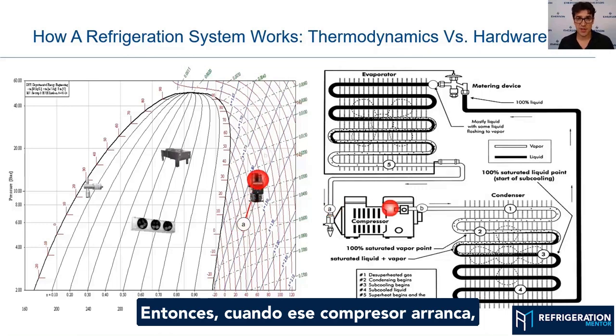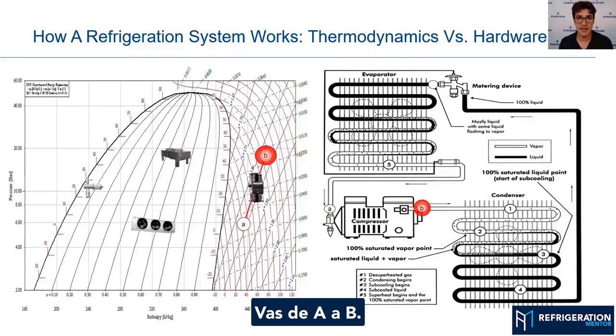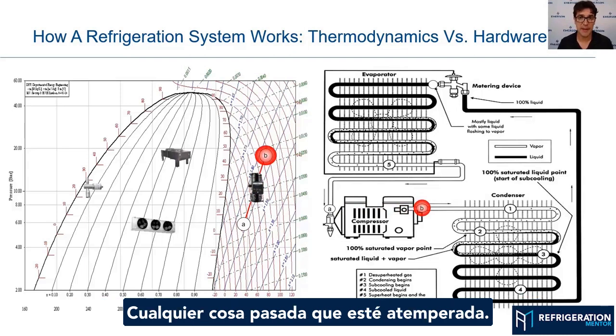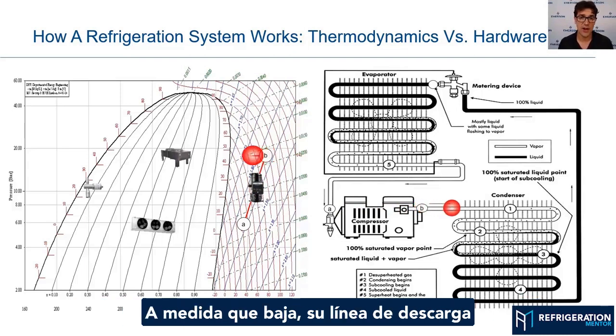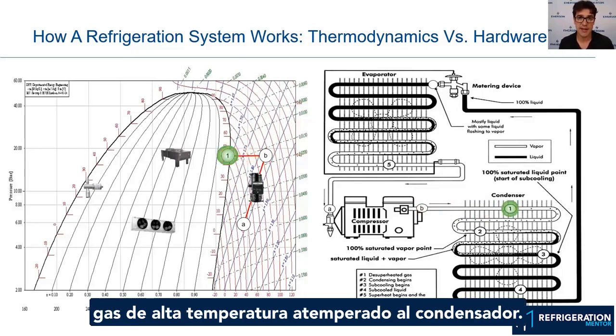As that compressor starts up, you have heat of compression. You go from A to B. At that discharge port, that's the hottest point. Anything past that is desuperheated. So as it goes down your discharge line, it's desuperheated — high pressure, high temperature gas desuperheated to the condenser.